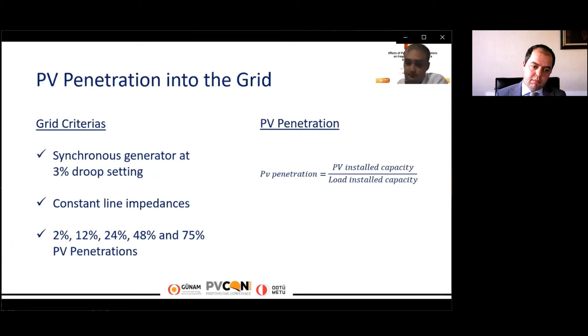And later on, we penetrate the PV systems into the grid. As you can see, PV penetration level depends on the PV installed capacity over load installed capacity. And we have a synchronous generator working at 3% droop setting constantly. And we have constant line impedances for strong and weak grid separately. We penetrate the PV systems from 2% up to 75% PV penetration levels. And we observe first frequency deviations.